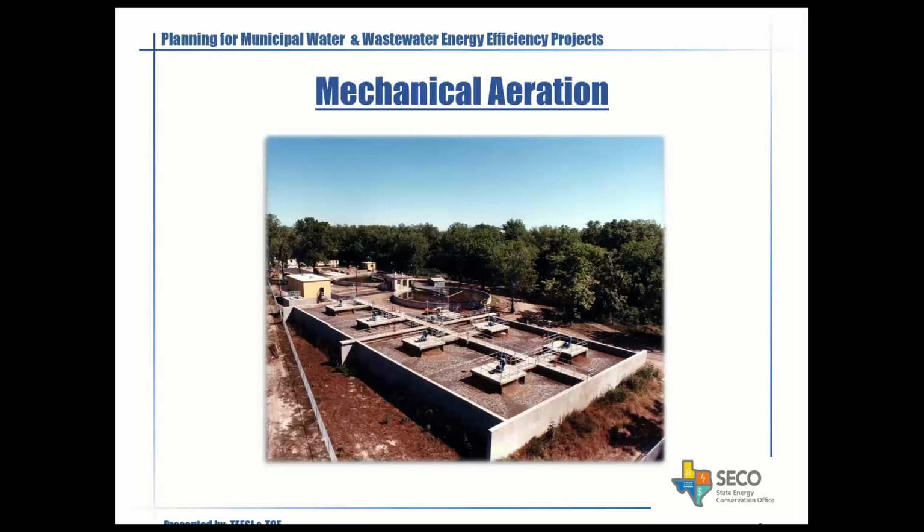Here's a photograph of a wastewater plant that uses mechanical surface aeration. People are getting away from this, but it's still a very efficient process. And these mechanical aerators, I have them in service at one plant for 30 years. They are just built to last a long time.